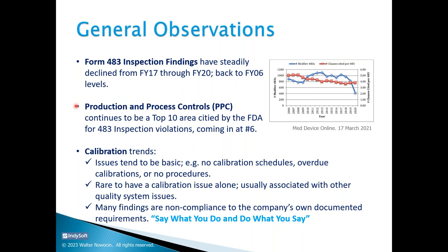Production and process controls, which is where calibration falls under, continues to be a top 10 area cited by the FDA, actually coming in at number 6. Calibration trends tend to be very basic: no calibration schedules, overdue calibrations, no procedures. It's rare to have a calibration issue alone; usually the findings are associated with many other quality system issues.